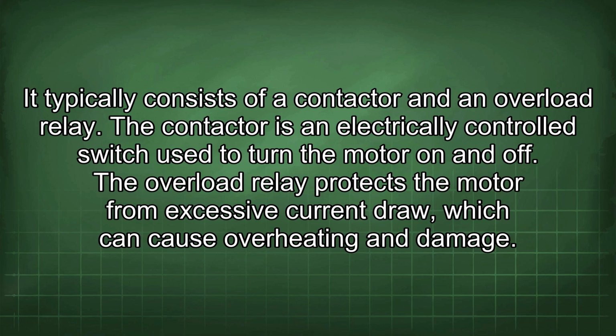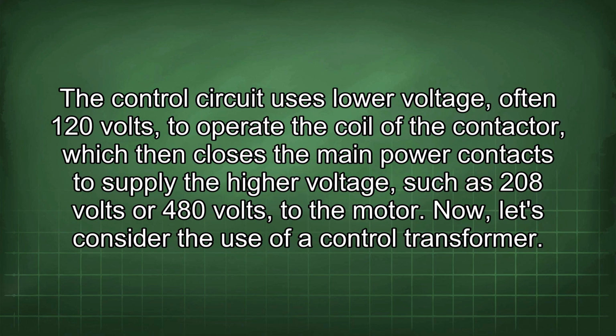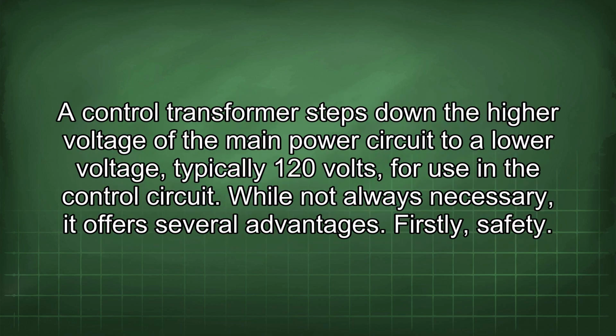The contactor is an electrically controlled switch used to turn the motor on and off. The overload relay protects the motor from excessive current draw, which can cause overheating and damage. The control circuit uses low voltage, often 120 volts, to operate the coil of the contactor, which then closes the main power contacts to supply the higher voltage, such as 208 volts or 480 volts, to the motor. Now let's consider the use of a control transformer. A control transformer steps down the higher voltage of the main power circuit to a lower voltage, typically 120 volts, for use in the control circuit.